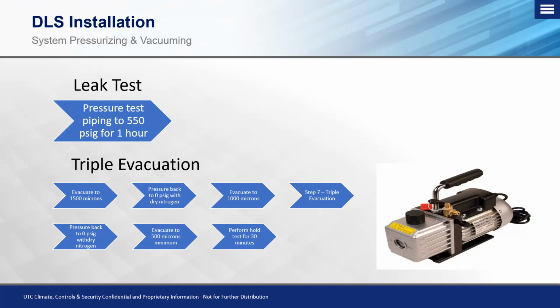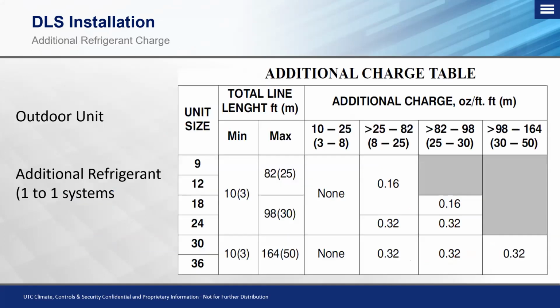Most of the time, we're typically right around 250 to 350 range for microns that we're holding for at least 30 minutes. And of course, you want to make sure that you document it and timestamp it so that you guys cover your butt to make sure that you know that the system was pressure tested and also dehydrated properly.